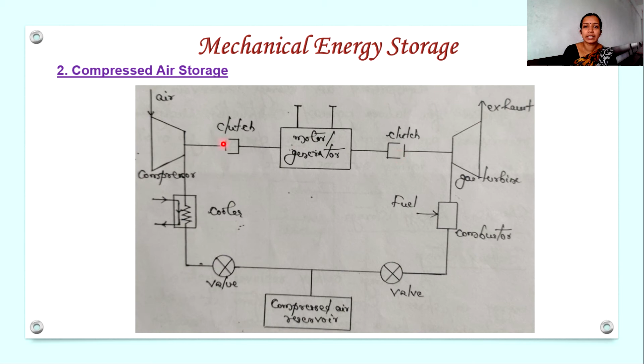So here see this clutch. So these clutches are used for coupling, connecting or disconnecting this motor generator unit with the compressor and the gas turbine. That is, while compressing, the turbine side must be disconnected and the compressor side connected. And while generating electricity back, the compressor must be disconnected and the turbine connected. So that is the purpose of the clutch.